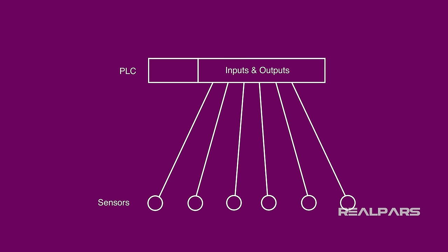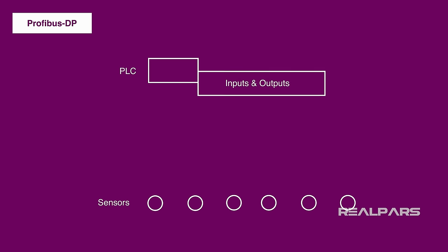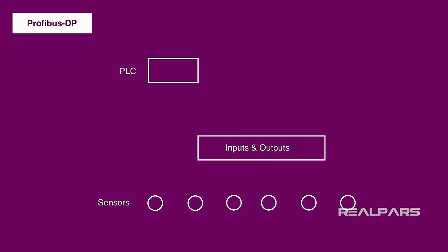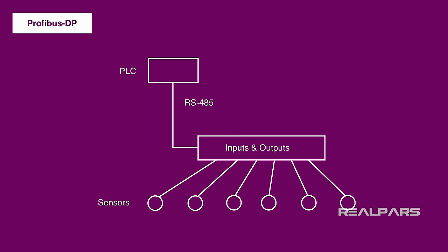The better way is to use the Profibus DP, and here's why. Profibus DP allows you to move the PLC inputs and outputs to the factory floor and connect them to the sensors. You can connect the IOs to the PLC using a single RS-485 cable, then use shorter cables to connect the IOs to the sensors. The setup is far cheaper and much more efficient.